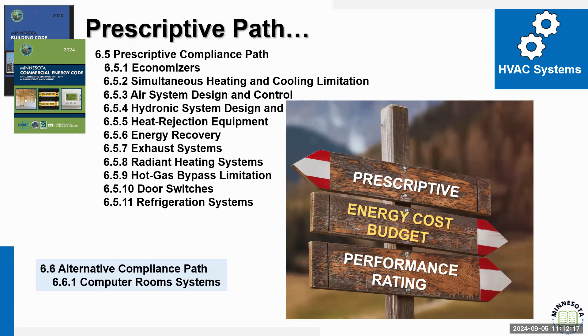We start talking about what makes a computer room or IT equipment room, and what are the expectations of those spaces, and how they're going to affect mechanical system designs. When we talk about air economizers, when are they expected, and more importantly, the impacts for controls and shutdowns associated with them. We want to make sure that in climates 6 and 7, if we're having cooling capacity over 54,000 BTU, we're incorporating an economizer.